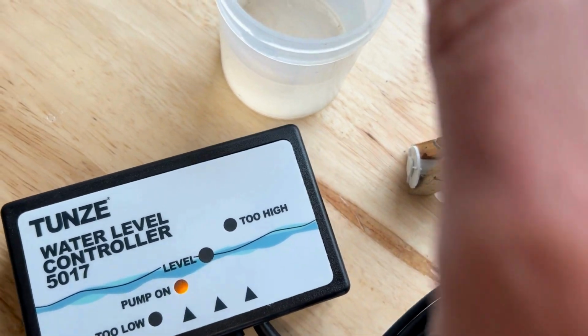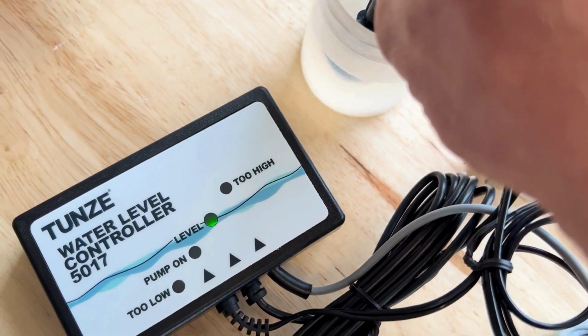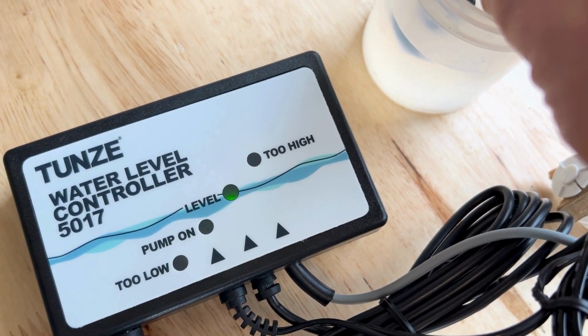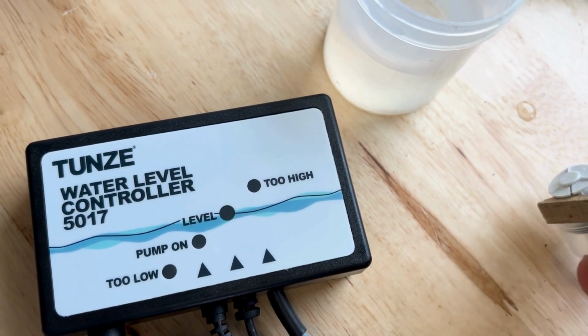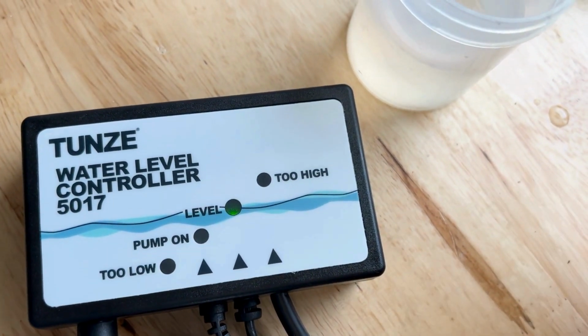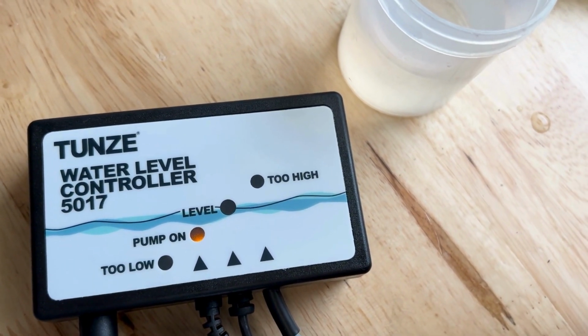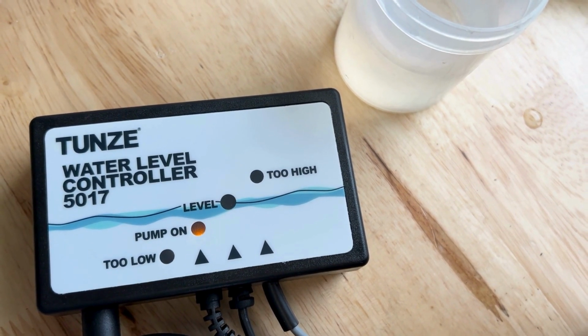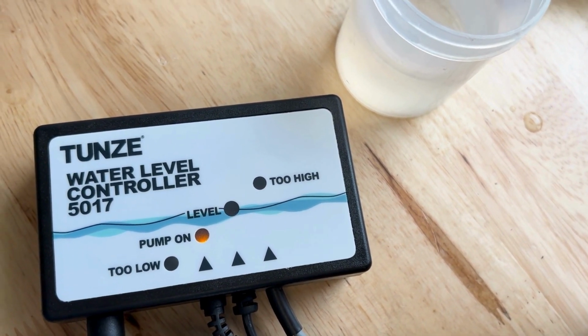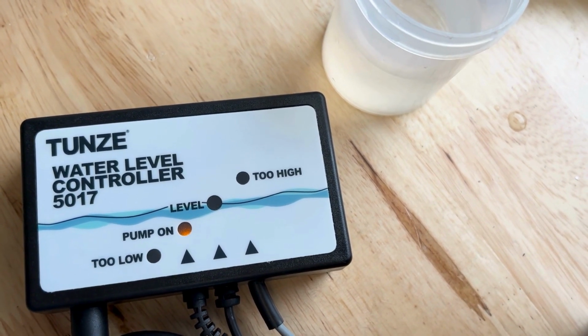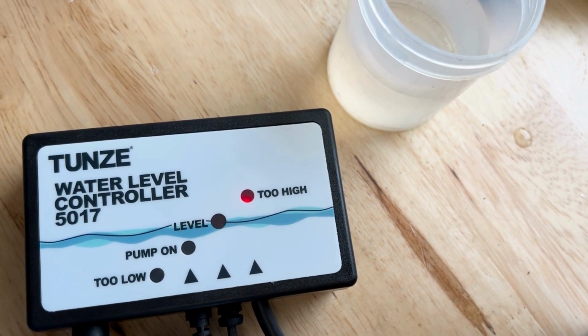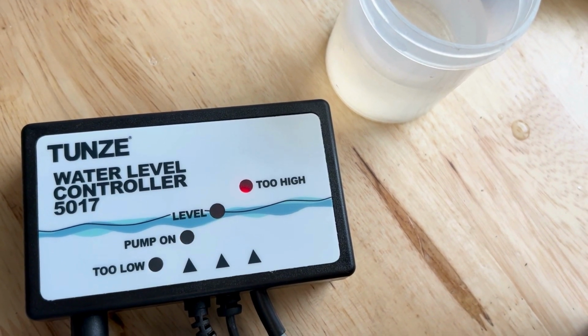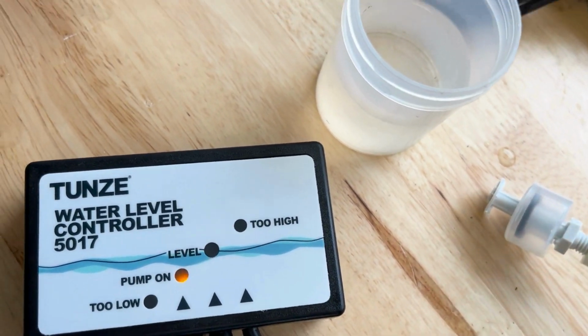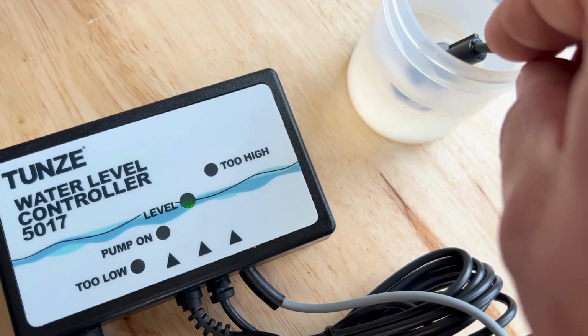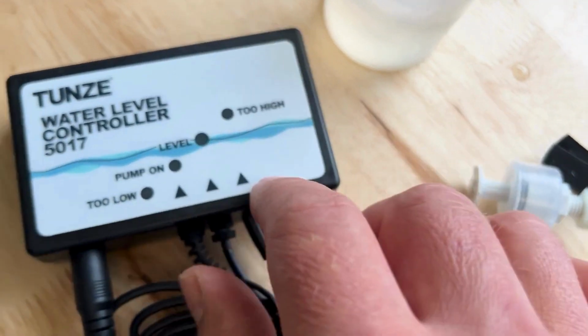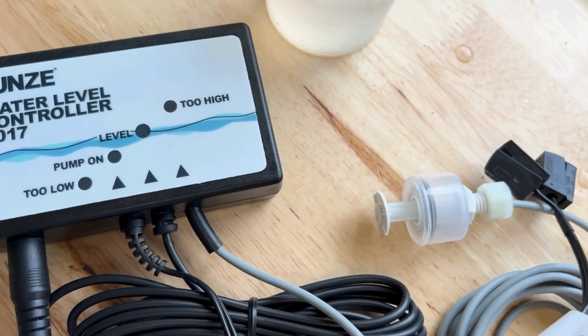Right now it shows pump on. We put our optic sensor in water. It goes to level. We can also check our float switch. By the way, the green flashing light means that it's in a time delay. It's detected that it's no longer in water. It's waiting 5 seconds to make sure that's not just a splash or wave. It does the opposite when water touches the sensor, but we can see our too high. I turned off the alarm earlier, so that's why we have no alarm. So all our sensors are functioning well, which would be expected. It's a brand new unit. But this is a way to check it.